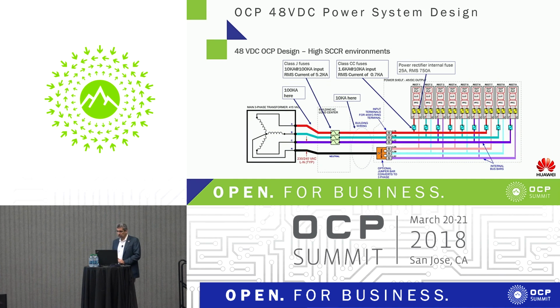This shows more details on that arrangement. You could have a 100,000 amp design, and then go through our fuses, the current limiting fuses, which reduce that to 700 amps, and then our internal fuses protect the equipment internally. This is the way to coordinate the current protection as you go through the product.